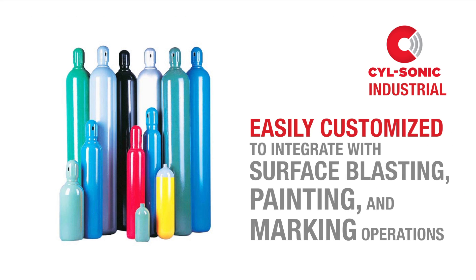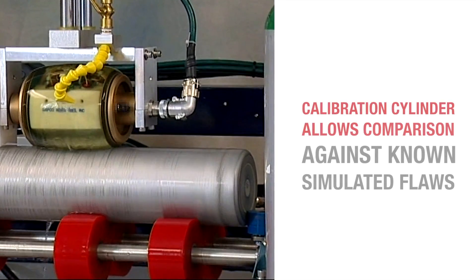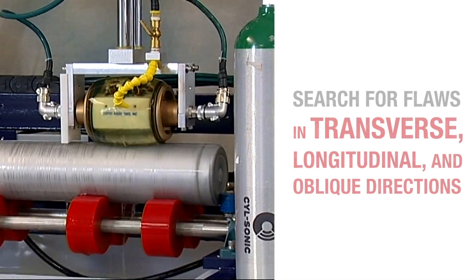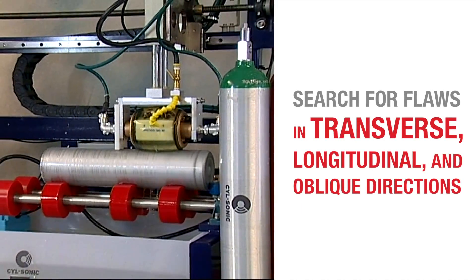The Industrial can be easily customized to integrate with surface blasting, painting, and marking operations. Cyl-Sonic employs a calibration cylinder that allows comparison against known simulated flaws. In addition, the ultrasonic wheel probe includes nine complementary high-frequency transducers that search for flaws in transverse, longitudinal, and oblique directions.